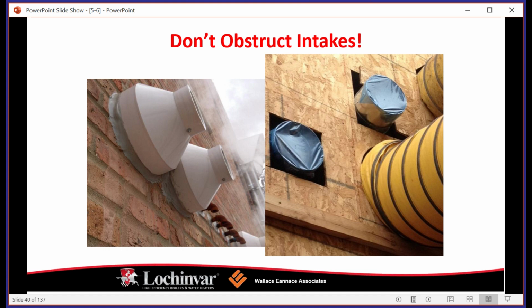Here's a couple good ones. So this is a better picture on the left-hand side of a concentric vent kit. So again, you use one penetration for your flue and your air intakes. The flue gas is going to be the portion that is pushing the smoke out. And if you look at this one, the masons were nice enough to go ahead and seal up what they thought was an aesthetically unpleasing gap between the wall and this piece of equipment. However, what they did do is completely isolate the boiler from any fresh air intake.